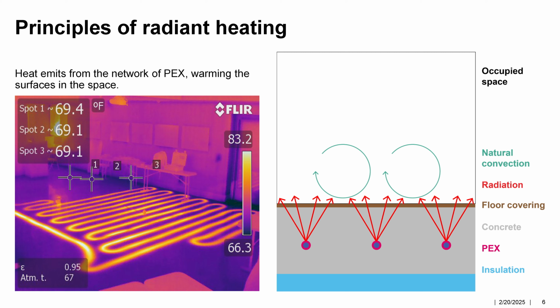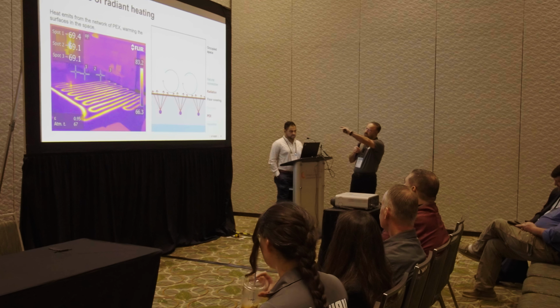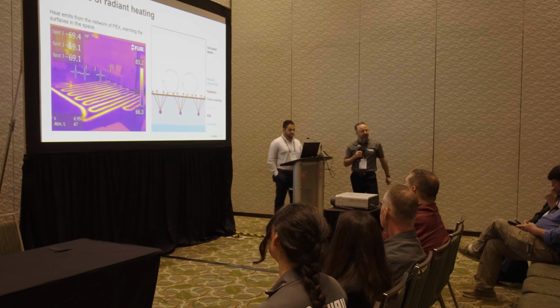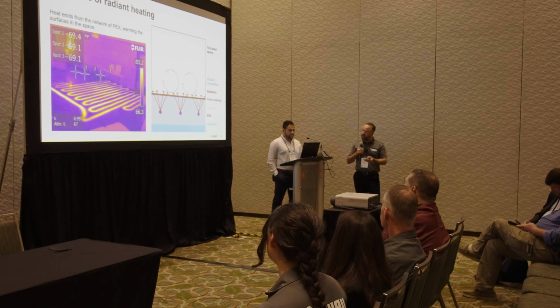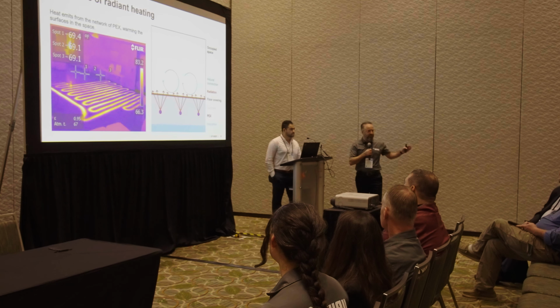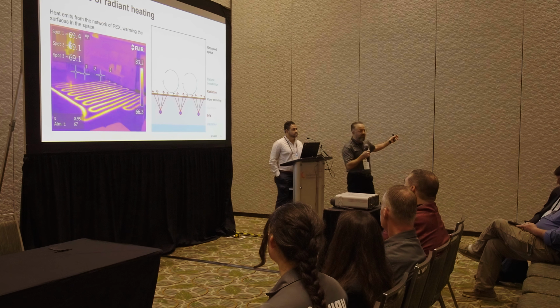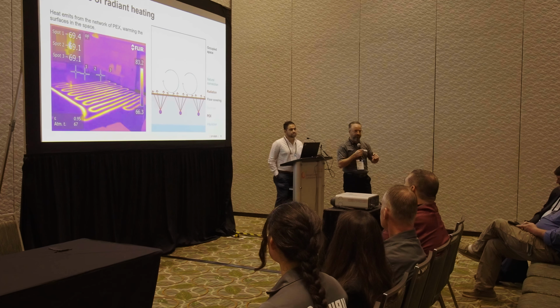So I have a hard time sometimes switching back from imperial to metric. It's going to be around 50 degrees maximum Celsius. You send the water through the network of the pipe, some sort of conduction heat transfer happens there, and then we try to get the temperature of the surface to the level that it starts radiating towards subjects in the room, towards the surfaces in the room, and towards the occupants.